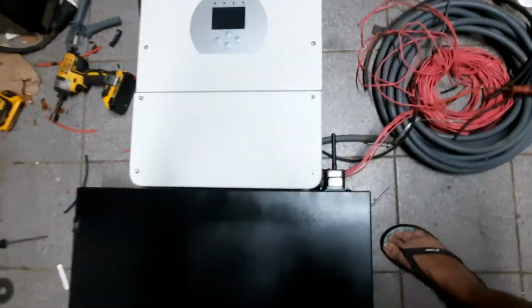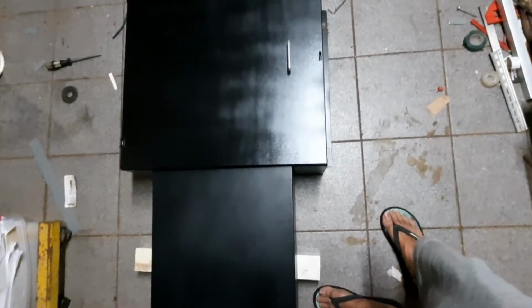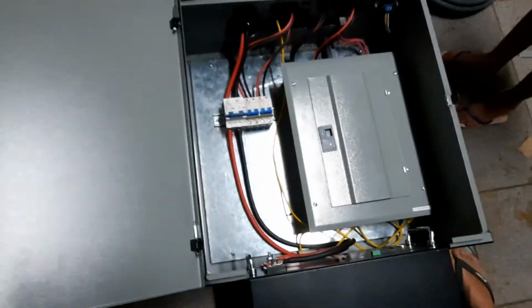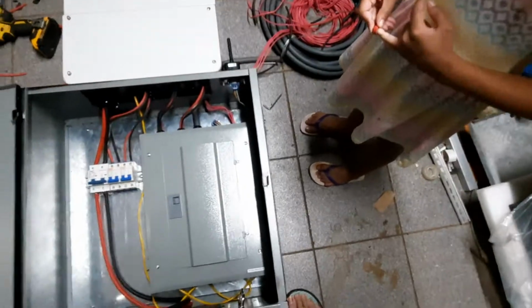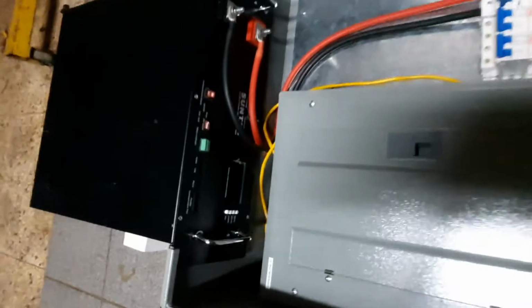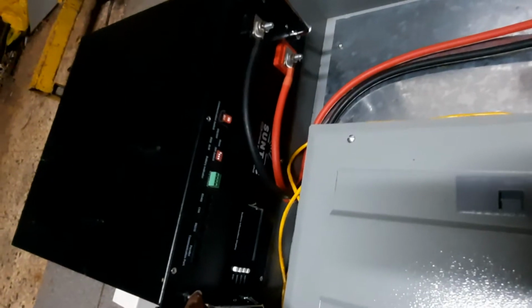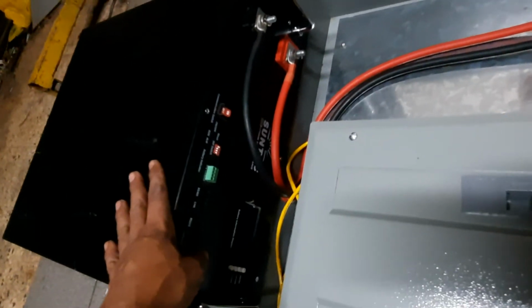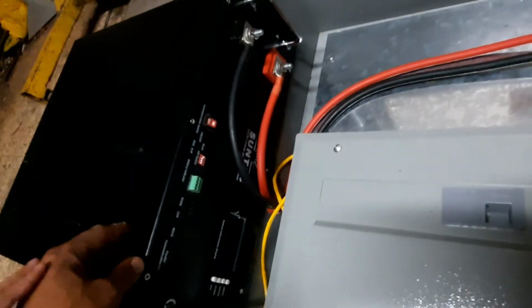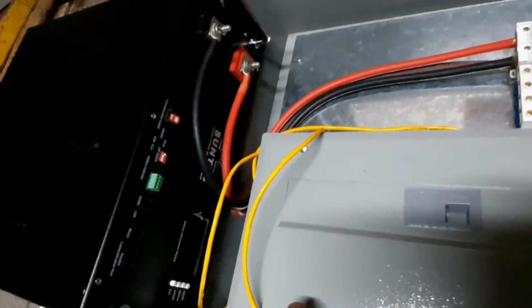And we'll have the Suntech inverter, and they aren't using an old crappy lead acid battery. What they're using, yes, this is the interior, a much cleaner setup than what I had. What they're using is another Suntech lithium battery. This is a lithium iron phosphate. This is a 5 kilowatt hour battery, a little bit more than 5 kilowatt hour, but just about 5. What we have here is going to be communicating via CAN.